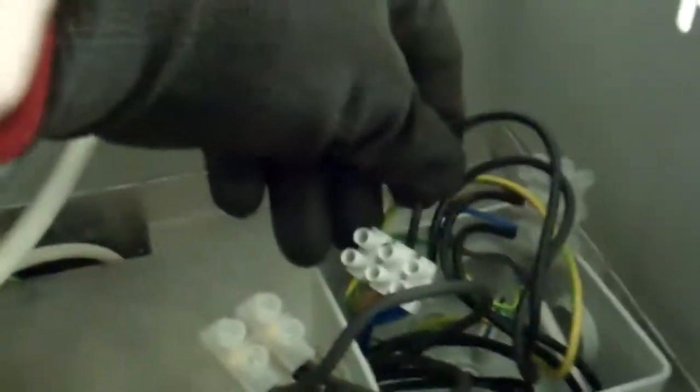Right, we've got two heaters here. Might have one in the drain panel, I'm not sure, don't think so. They run off of three and four. One and two are on the fan motors.